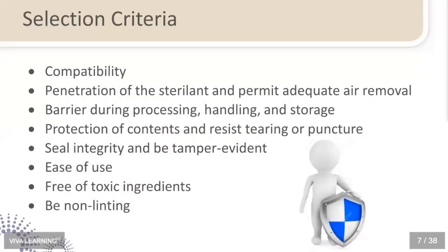When you're selecting sterilization products, packaging products, there is a list of criteria that you want to use to ask, how does this meet up? How does it compare? First of all, the simple thing is you want to make sure that it has in fact been cleared by the FDA for use. I had somebody call me that was doing dry heat sterilization, and they were concerned because their packaging was catching fire. What I ended up finding out is that they were using brown paper lunch bags in a dry heat sterilizer. Obviously not an FDA approved, or excuse me, FDA cleared device.